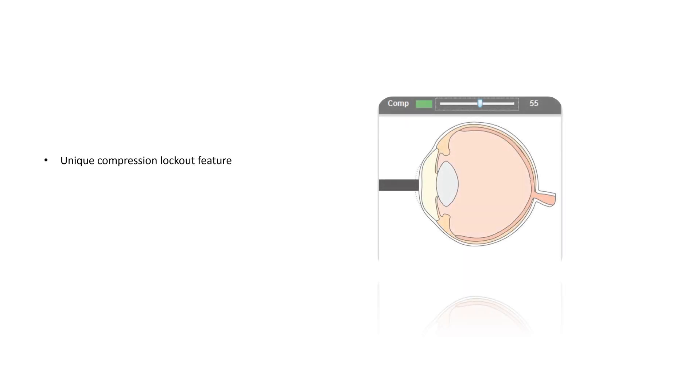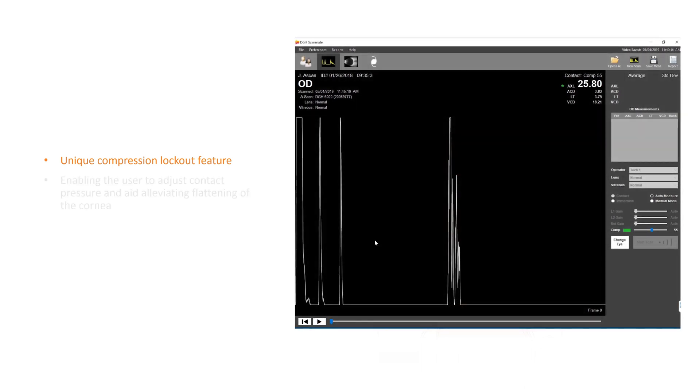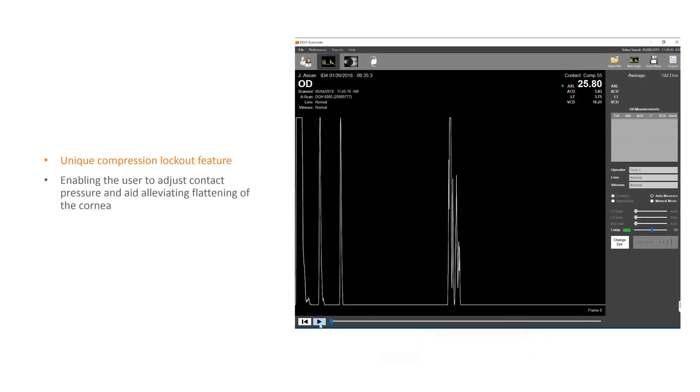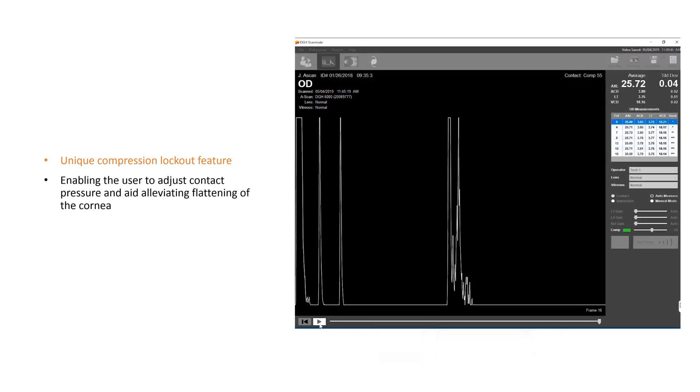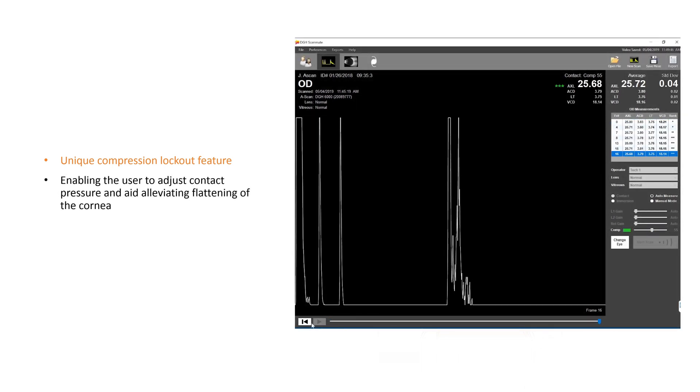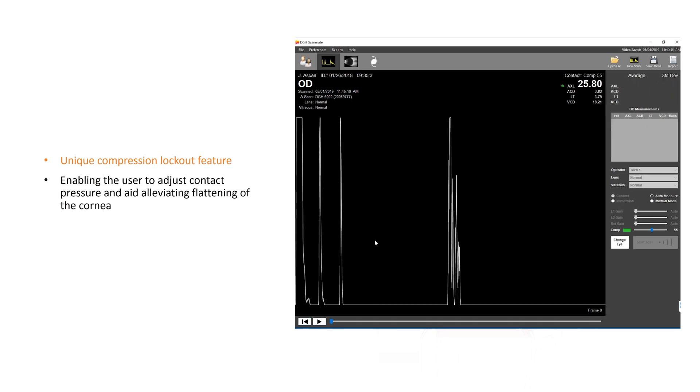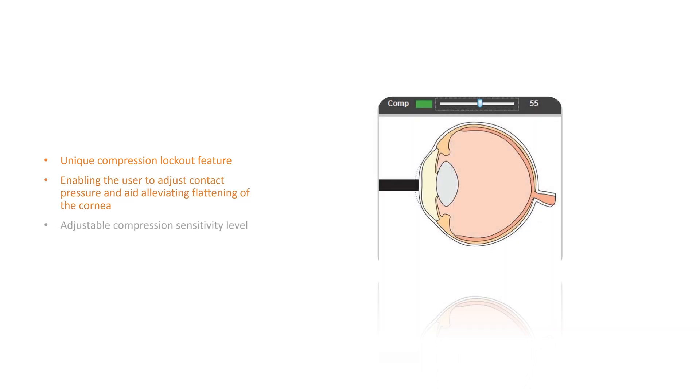A unique lockout feature for use during contact measurements. When enabled, compression lockout will stop the system from measuring waveforms which show indications of corneal compression. Audible tones are provided to guide the user in adjusting contact pressure and aid in alleviating flattening of the cornea.